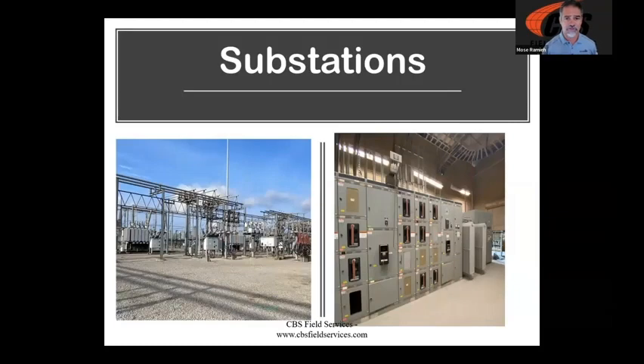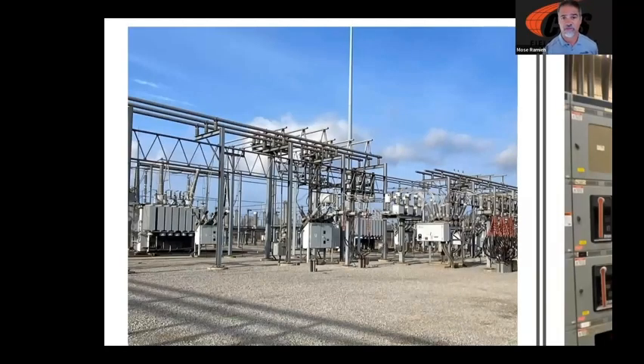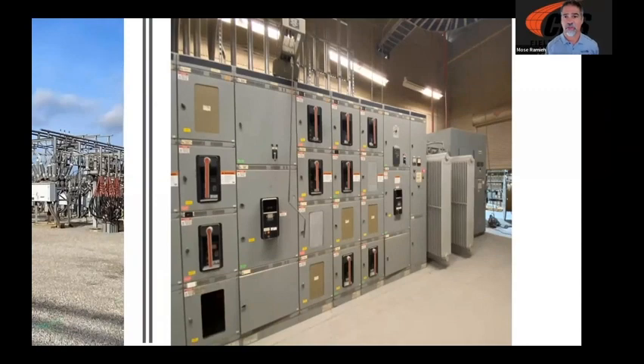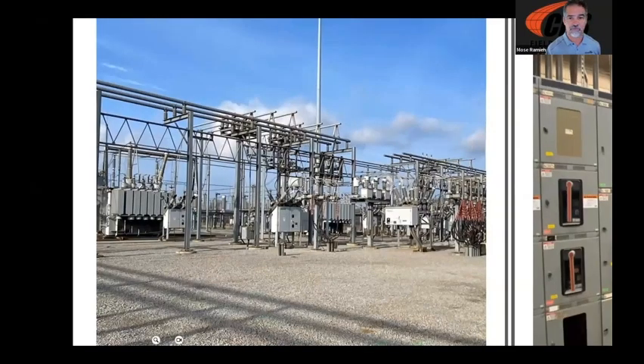Substations come in a couple of different varieties. Some of you have substations with a great big chain link fence around them, lots of outdoor bus work, switches in the air, breakers on the ground, things of that nature. Some of you might call this a substation. On some level, they're made up of a lot of the same basic components. Over here, we have a transformer. Over here, we have a switch. Next to it, we have a liquid filled transformer. Inside this box, that same bus work, those same pieces, those same insulators are all inside. And then we've got our breakers here. As you can see, it's a very similar situation. We've got the bus work, the breakers, and our liquid filled transformer.